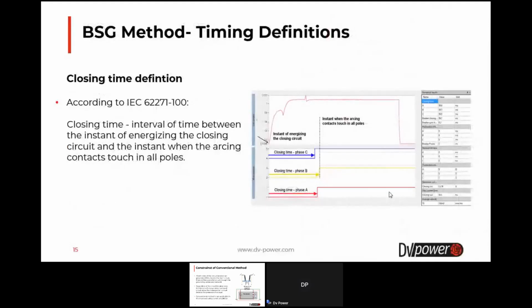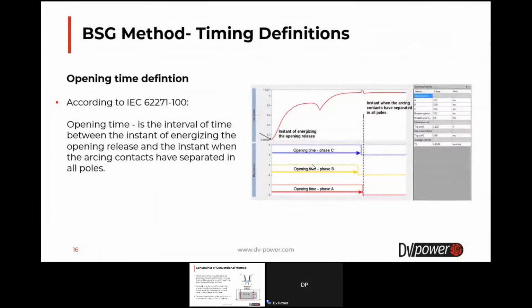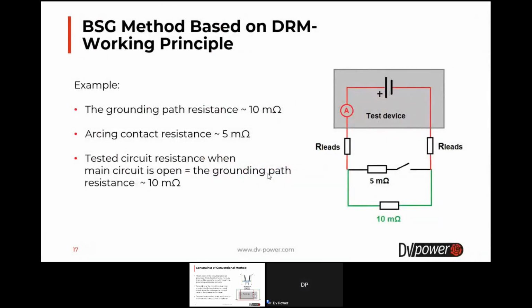So, as you can see, according to the IEC standard, closing time is the interval of time between the instant of energizing the closing circuit and the instant when the arcing contacts touch in all poles. And it is shown in one graph here. According to the standard, opening time is the interval of time between the instant of energizing the opening release and the instant when the arcing contacts have separated in all poles. So this is the reason why the instant of the arcing contact separation or touch should be detected, not the instant of the main contacts touch or separation.